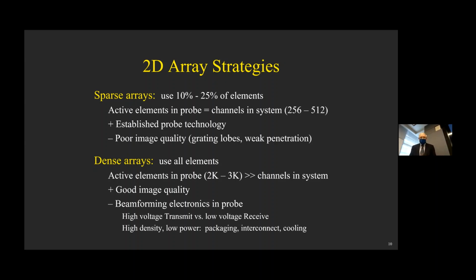A lot of times that means a relatively high voltage for transmit, much lower voltage to receive. So the ASICs that you end up dealing with there are sort of unusual in that most common signal processing ASICs are all low voltage things, and then high voltage things are usually separate in a different semiconductor process. You end up with the standard sorts of packaging problems that are listed here.